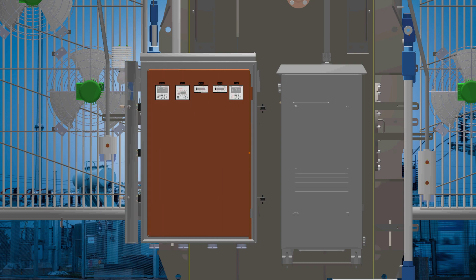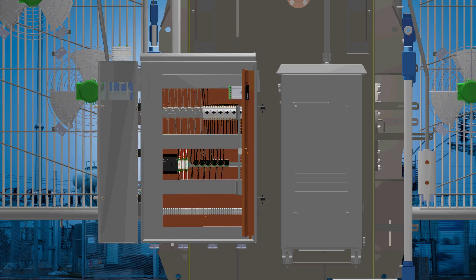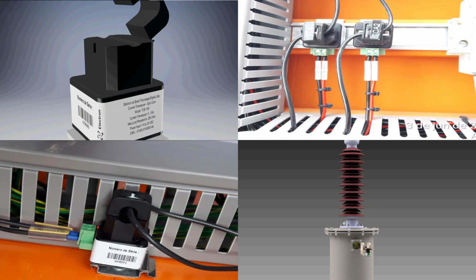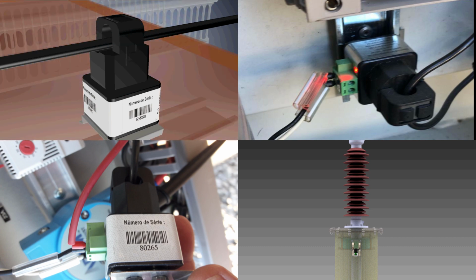That is, thermal image of the transformer continues, without the need for opening the TC secondary contacts, and thus, avoiding any kind of burning and contamination of oil, unavailability and high-risk accident for maintenance operator.